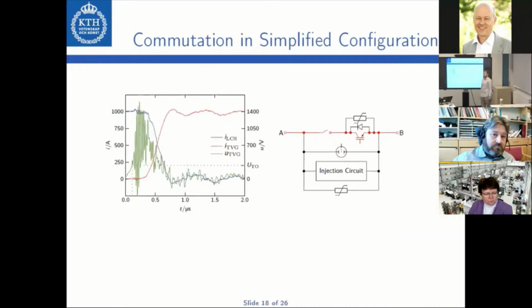In the next step, we analyze the simplified configuration. In this state, the main path conducts. In the next step, the LCS is turned off. The snubber of the LCS starts to conduct, and it forms the turn-off voltage of the LCS. In this state, the ultra-fast disconnector or mechanical key switch is still in its closed state. This means that the voltage of the snubber also appears across the terminals of the triggered vacuum gap. The voltage measured across the triggered vacuum gap corresponds to the green line here. The blue line is the current in the LCS, and the red line, the current in the triggered vacuum gap.